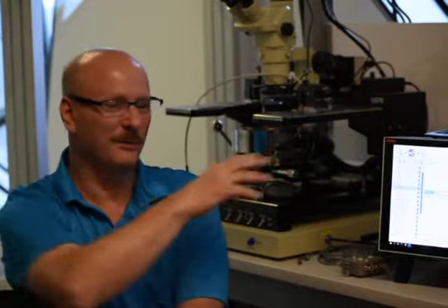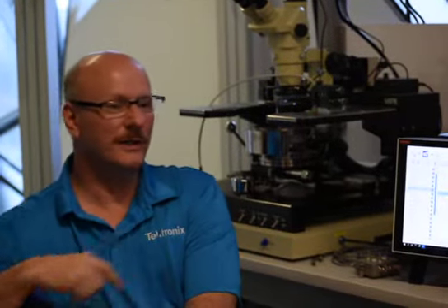If you've got multiple machines, maybe that makes sense. But a lot of people will use a local calibration lab, and they'll tell you that they can do it, but guess what they're going to do? They're going to send it to us. You need a very high-end metrology lab to calibrate this equipment because of its sensitivity, reading the femto.